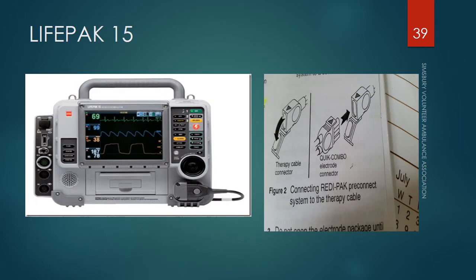Now, the adult pads that are in the LifePak 500 AED can attach to our LifePak 15. I've shown you a picture of the LifePak 15 that we carry without the case around it. And you can see, just off to the right, I've demonstrated that the electrode on the QuickCombo pad connects directly to our LifePak. On the bottom right corner of the LifePak, you can see a little cord or wire, and that wire has a little opening, which is pictured in the picture on the right side of the screen, and it's called the therapy cable connector. Basically, the top just flips open, and then we take the QuickCombo electrode. There are 2 little triangles on the top. The triangles meet each other to make an hourglass.